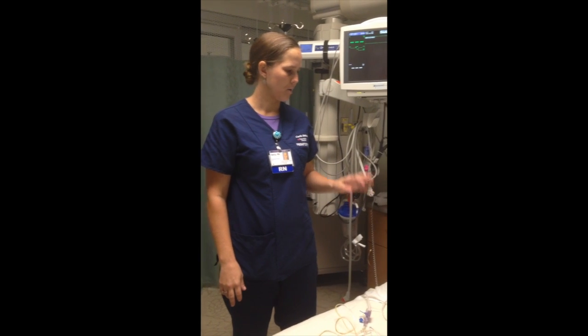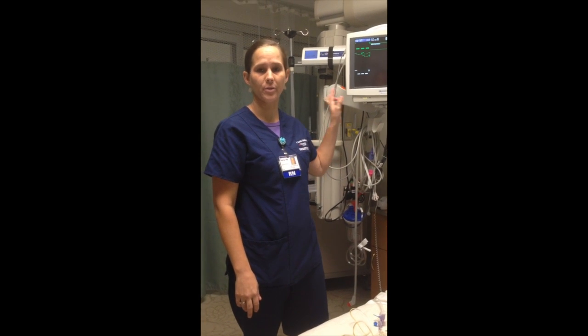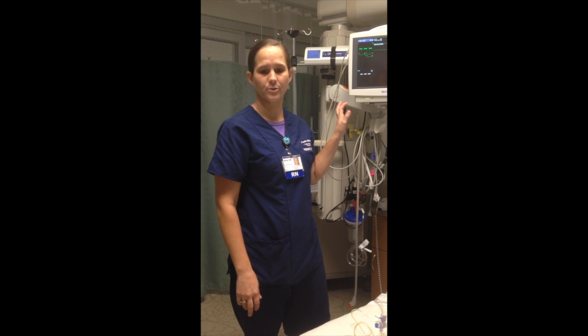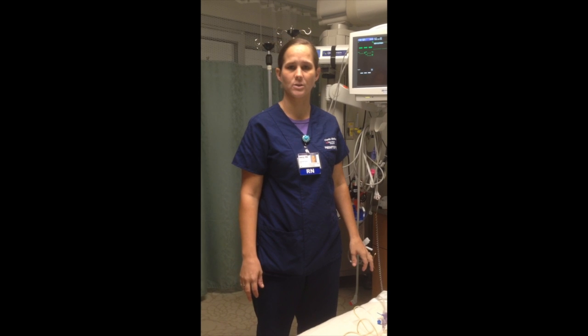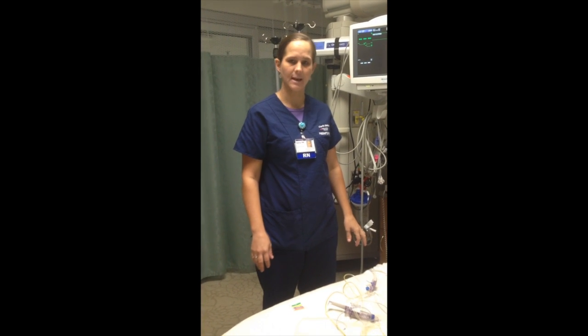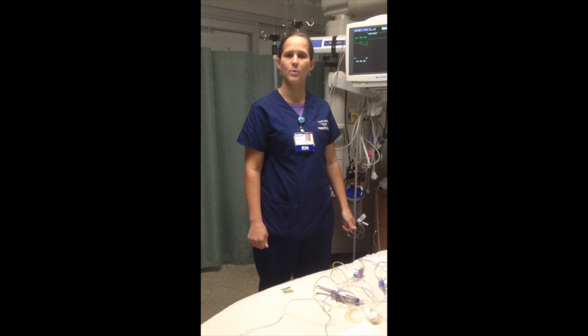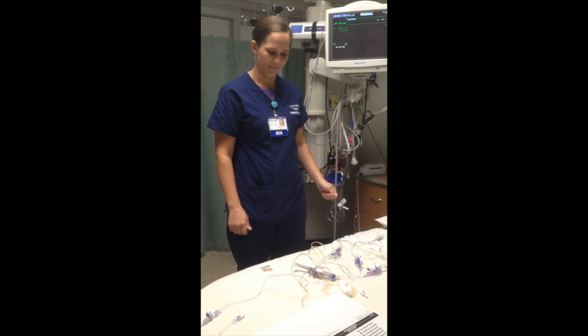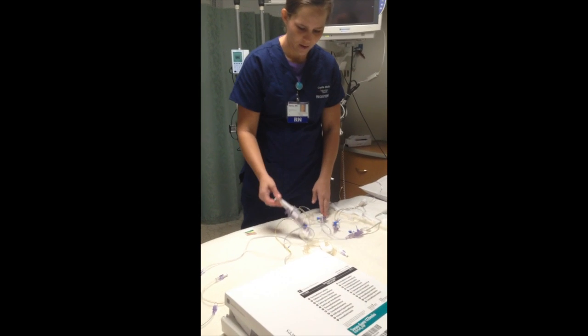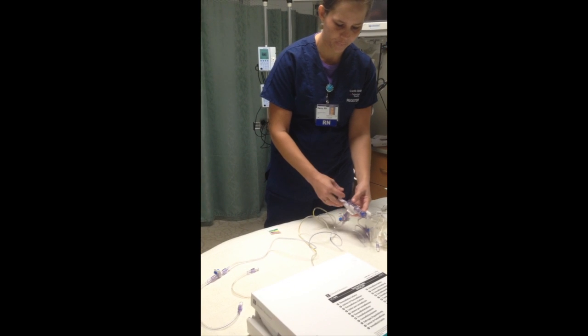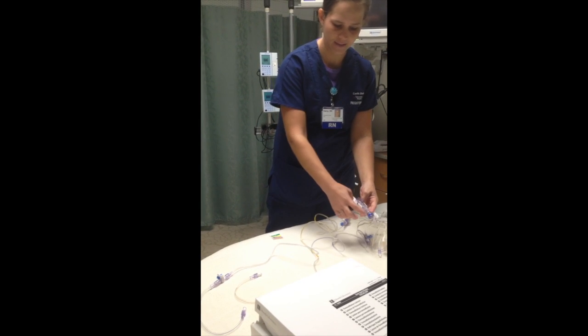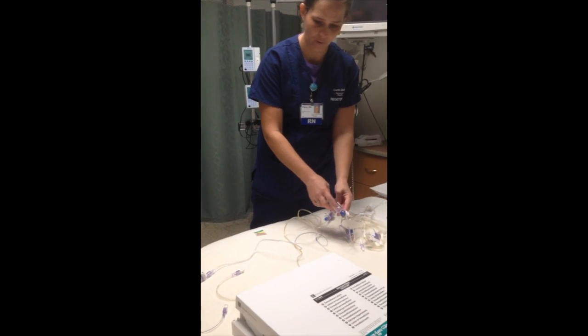In this segment of our video, we're going to review how to set up our pressure cables to the monitor, label them correctly, have everything zeroed. All of this needs to be done prior to the physician coming in to insert the Swan. It's important to have everything ready so that when he comes in, we can just insert and go. A few things: when you're priming, you need to make sure that the vamp has no air in it either, and it's been fully primed.